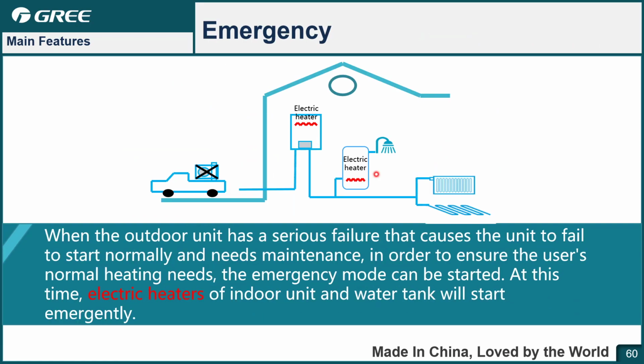Next one is the emergency function. If the outdoor unit is malfunctioning and needs to be repaired, you can set the emergency setting on the controller, and then the unit will use the optional e-heater and the water tank e-heater as the heat source so the unit can still generate hot water, and you get some troubleshooting time for the repair and for maintenance.